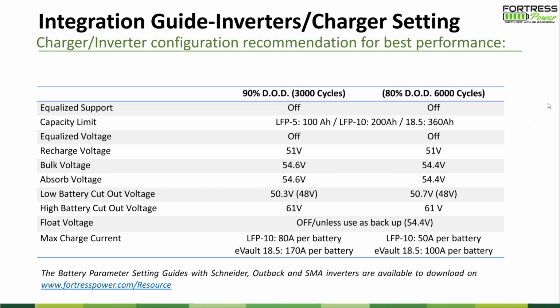Most 48 volt storage inverters will support three-phase charge processes, as I mentioned in the first slide's parameter settings. I'll leave this for you to read; it's very clear on the voltage setting. You might calculate a little difference if you have a long cable, since there's a voltage drop. Other than that, this is very good practice when doing system setup.